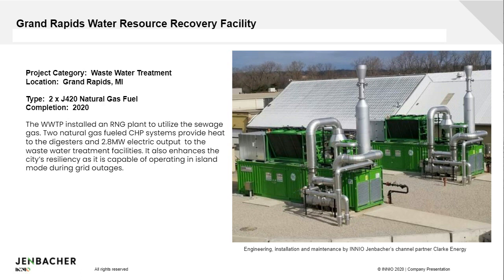Again, these are the Jenbacher factory containers you see there, the 40-foot containers housing the J420s with full exhaust heat recovery. On the bottom you see that silver exhaust heat recovery unit. The exhaust goes out of the top of the container from the engine, down to that exhaust heat recovery unit, which in this case produces hot water, though it would also be possible to produce steam, and then it goes back up onto the container where you have your silencer and stack.